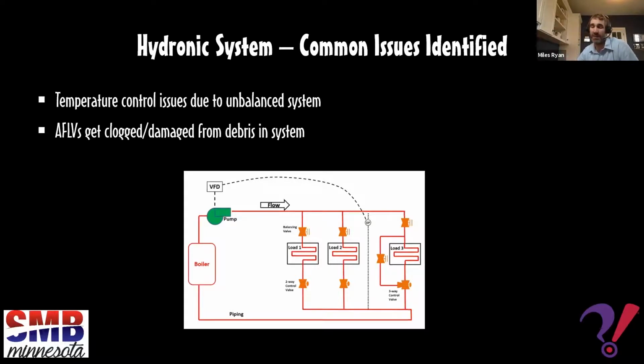And what it was is they didn't install any balancing valves in any of the fin tube radiation. And it just happened that the top floors were kind of the path of least resistance. So they always had adequate flow available when they wanted it at their fin tube radiation, and the bottom floor suffered. So our recommendation at the time was to install balancing valves to make sure everyone got their fair share of flow. And we gave some heat to the people who bought condos on the bottom of that building.